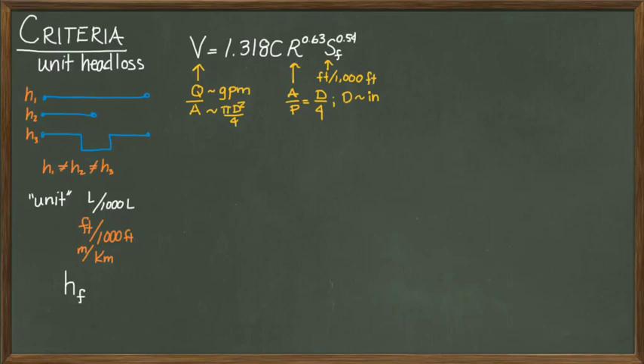I've covered the derivation of this form of the equation in another video, so I'll just mention here: the unit head loss equals (148Q / (C × D^2.63))^1.85.